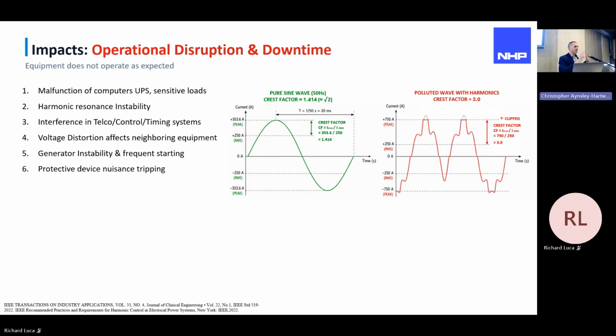So coming back to the real world, for your installation, if you have a thermal magnetic breaker, and everyone knows it's a bimetallic strip that's operating and bending according to the amount of current passed through it, and it's just responding to the heat. So we're just looking at the total current coming through, including the harmonic distortion, increased RMS. So we're going to get nuisance tripping if it is a thermal magnetic device. Whereas an electronic breaker is using internal CTs. So we're sampling at a particular frequency, getting the true RMS waveform, and then detecting on that waveform.